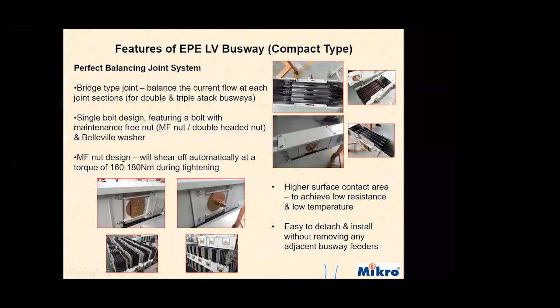This is our joint — the so-called bridge type joint, or single bolt design. We call it a double-headed nut, which will break off — so-called shear off — when it is fully tightened to a torque of 160 to 180 Newton meters. My colleague Shafiq will explain about the installation of this later.